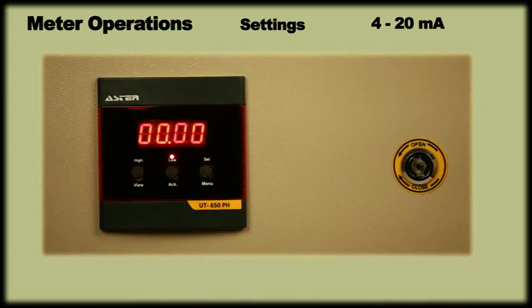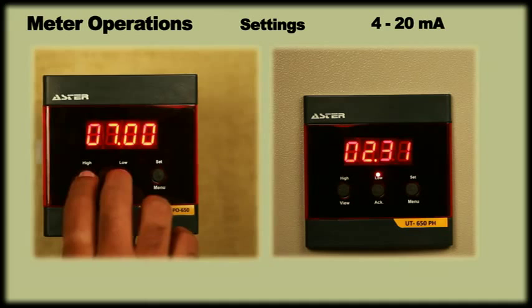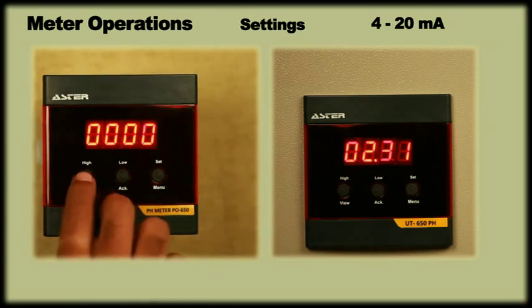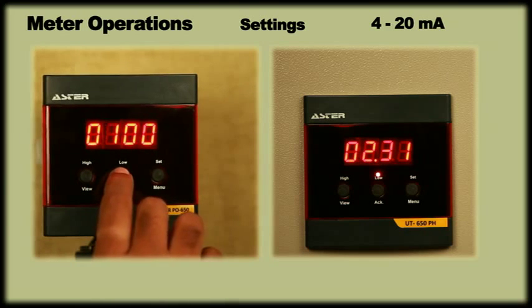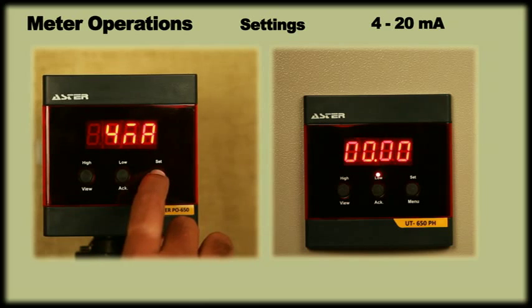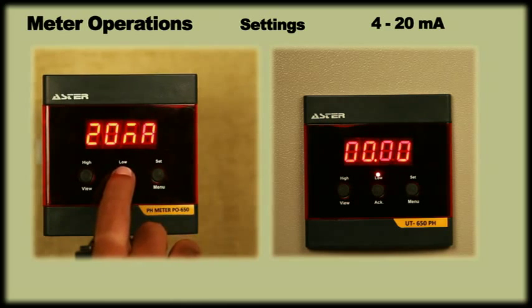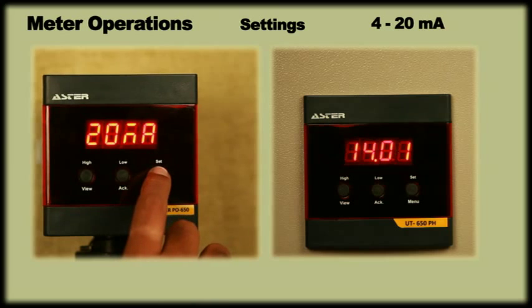Note: the meter has an inbuilt 4 to 20 mA output simulator for easy synchronization with the PLC or any other remote device. To output standard 4 and 20 mA, enter password 0420. Press menu twice to output 4 mA. Press ACK key and then menu key to output 20 mA and press menu twice to exit.